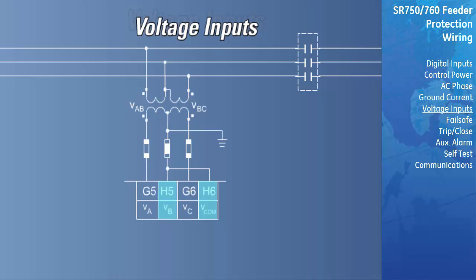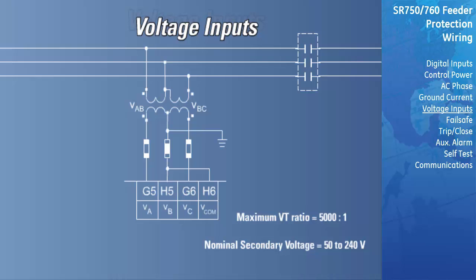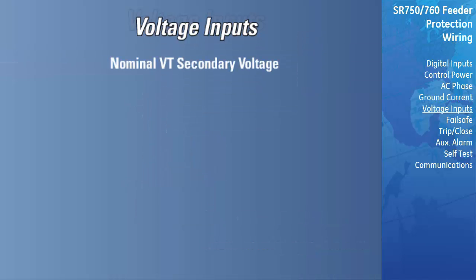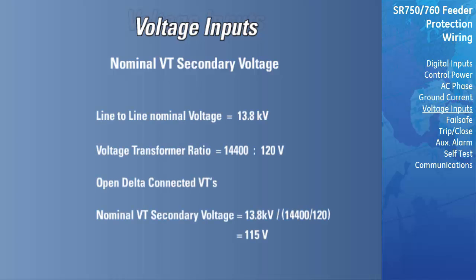Regardless of the wiring configuration for the bus VTs, there is a maximum VT ratio of 5,000 to 1 allowed, and the nominal secondary voltage must fall between 50 and 240 volts to allow proper metering and to protect the relay from damage due to high voltages. In order to calculate the nominal secondary voltage for open delta connected VTs, the system line-to-line voltage is divided by the ratio of the VTs installed. Consider a 13.8 kilovolt system with 14,400 to 120 volt VTs. The nominal line-to-line secondary voltage will be 13.8 kilovolts divided by 14,400 over 120, or 115 volts.